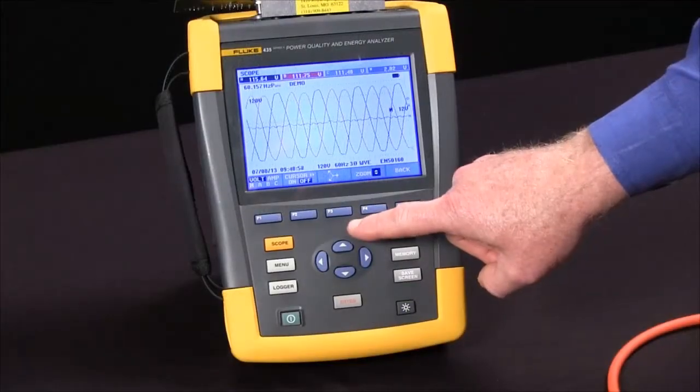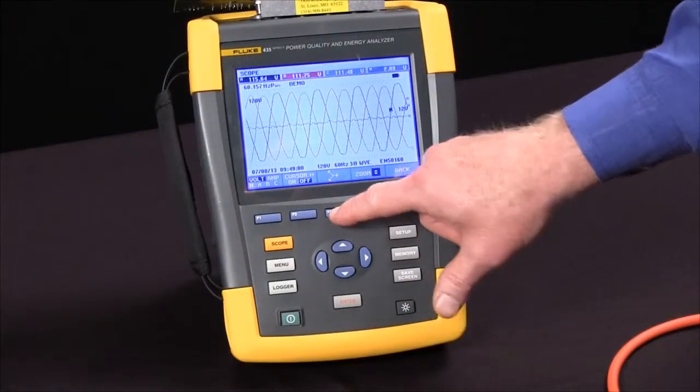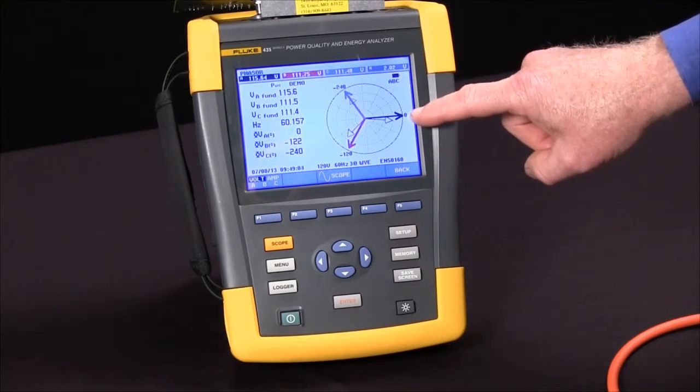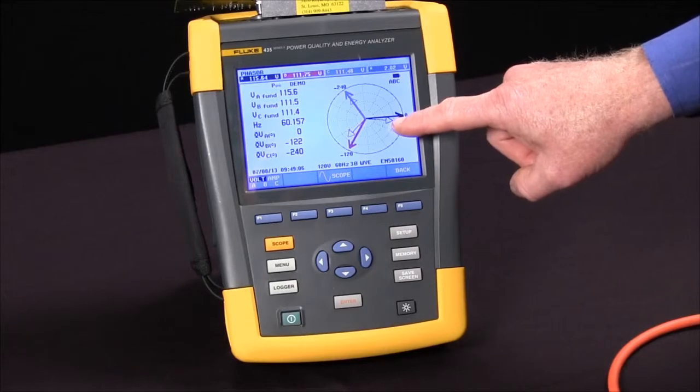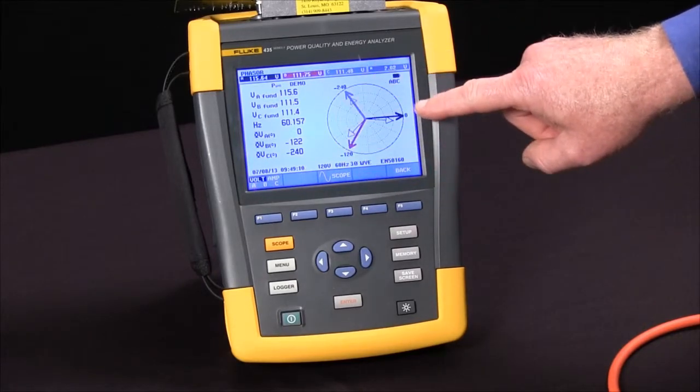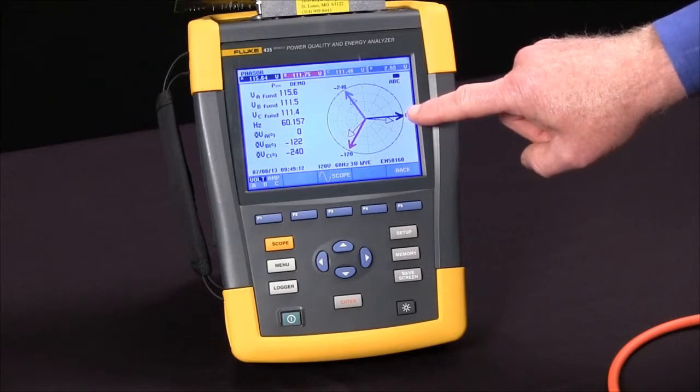If we use the F3 key to pick up a phasor view, we'll see some bold vectors for our voltage and some lighter vectors for our current. If things are properly connected, we should see those vectors being close to in phase with each other.